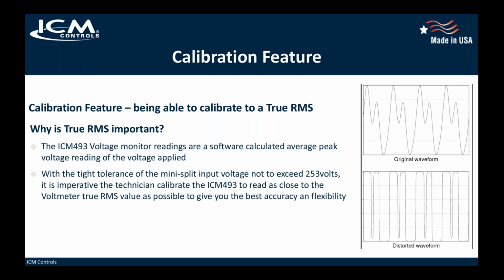We added that feature into ours as a software feature to calibrate to the true RMS reading, rather than actually having to put the sophisticated electronics in it that are required to be a true RMS meter. It wasn't necessarily required for this application. We just need to know what the peak value is, and then we can tune it to the RMS value so that you can be within about a volt of the true RMS reading of your voltmeter.